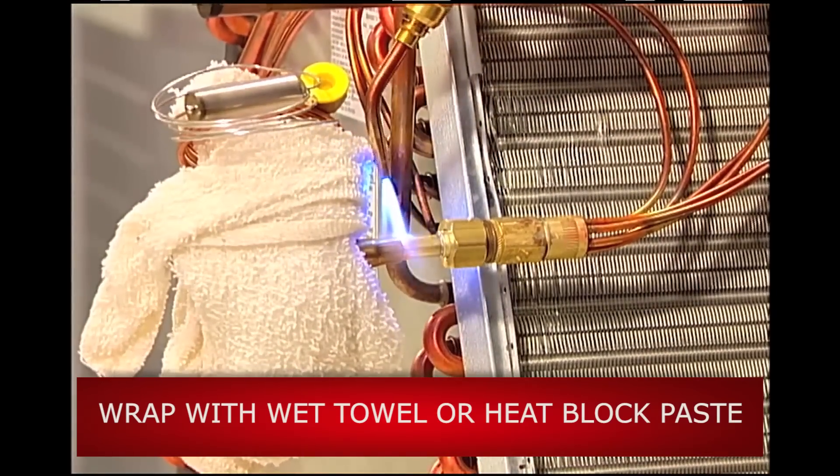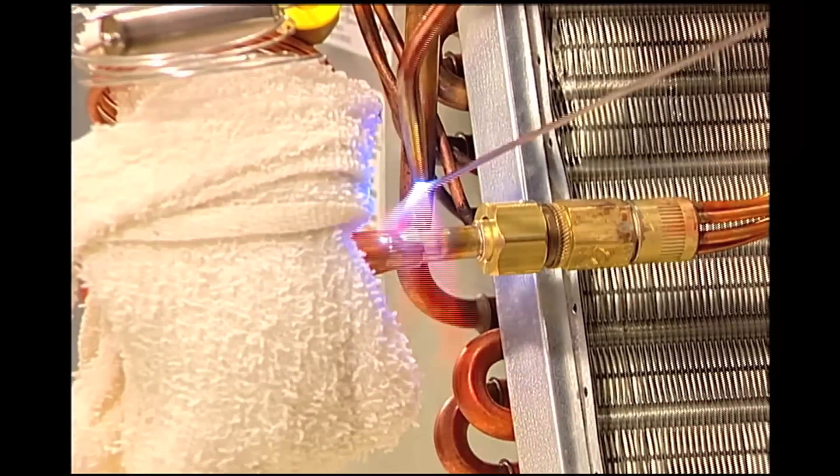Be sure to wrap the body of the TXV with a wet towel or use heat block paste to protect the internal components. Also, be sure to keep the sensing bulb and capillary tube away from the heat.